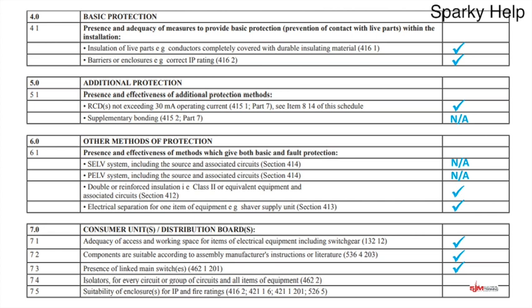Isolators for every circuit or group of circuits and all items of equipment. Hopefully that would be a tick. So can we isolate things, and circuit breakers can be used as isolators? Can we isolate pieces of equipment within your installation safely within the consumer unit and distribution boards? Yes, we would have done. Suitability of enclosures for IP and fire ratings. So the distribution board, if you put your distribution board outside, it needs to be rated for outside or in an enclosure that is suitable for outside.